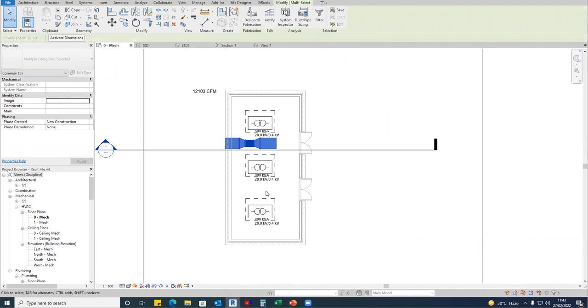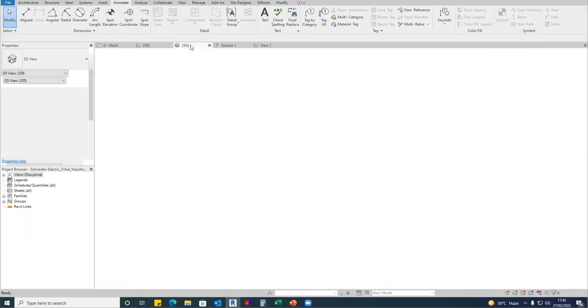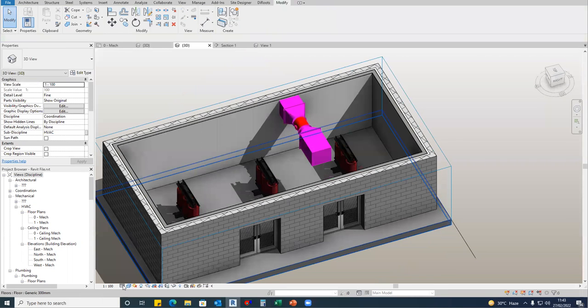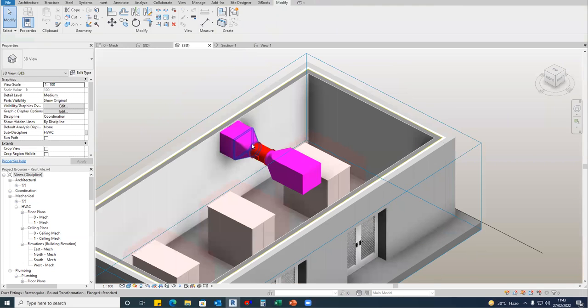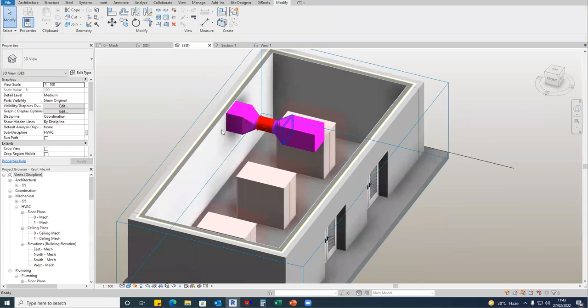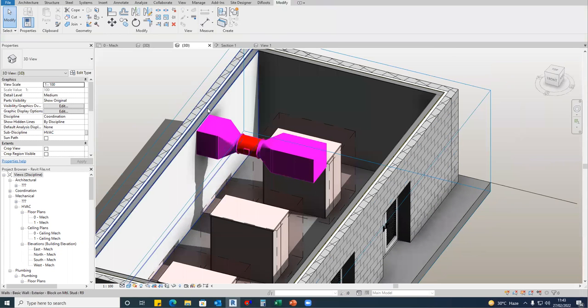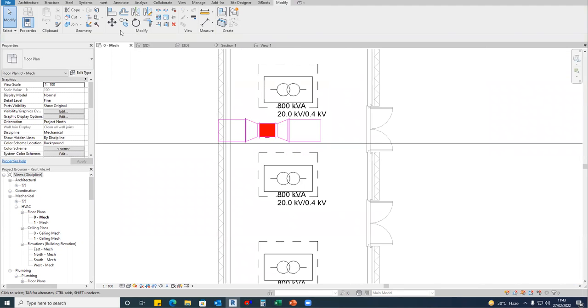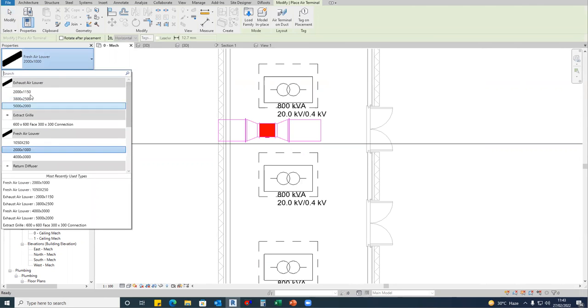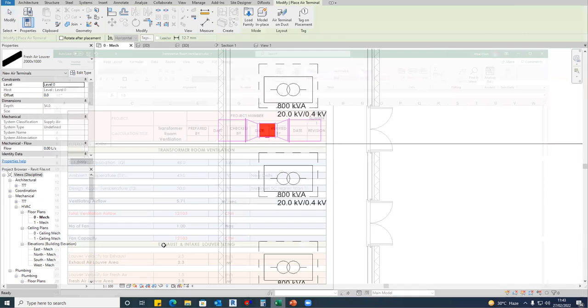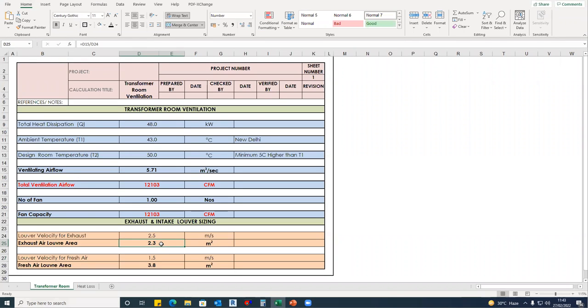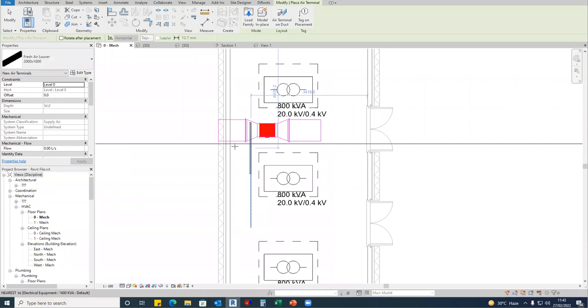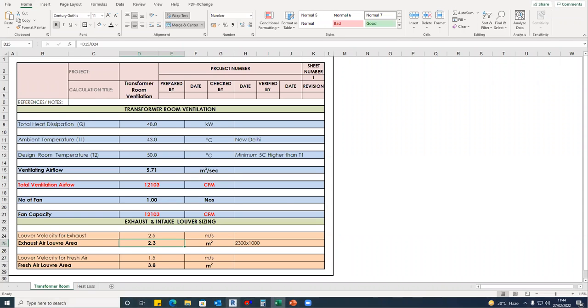Let's check the 3D view also. Not this one, this one, perfect. I'll make it medium. So this is your exhaust fan. In this, the thing which is left is the bell mouth and the louver for exhaust. So I'll take one air terminal, that is one exhaust louver. Exhaust louver, what is the louver area? This is 2.3 meter square. Okay, so I can take the sizes by 1 meter. This is the size I can take for this area. 2.3 into 1 will come out to be 2.3, so 2300 by 1 meter, correct.